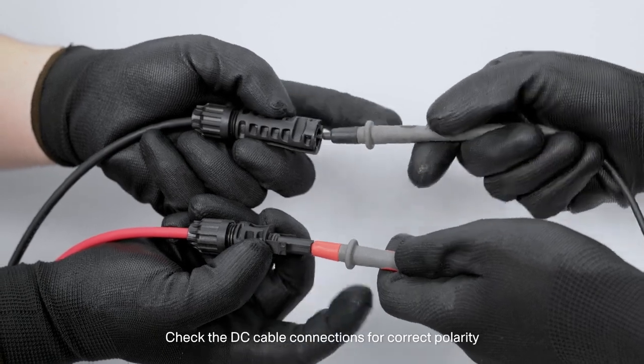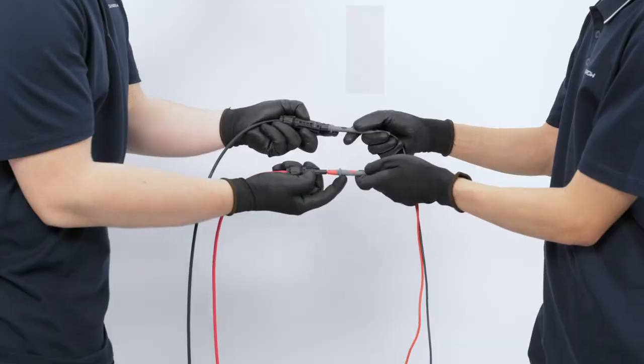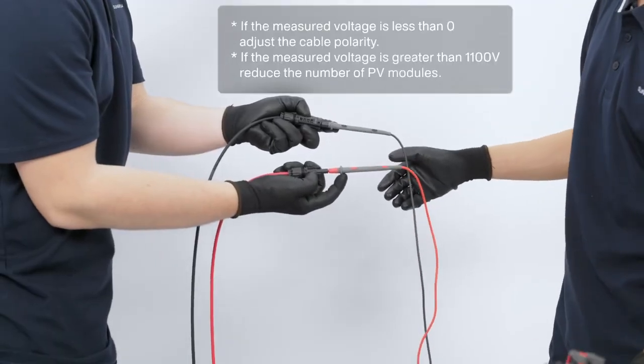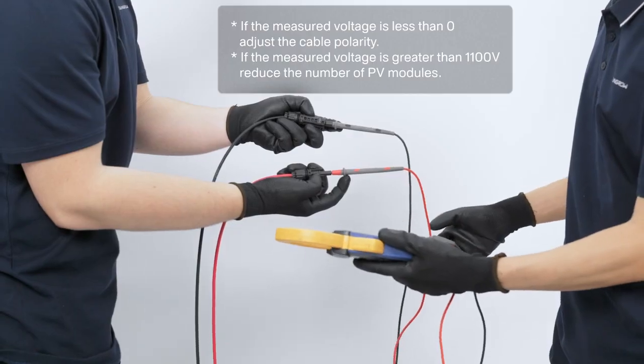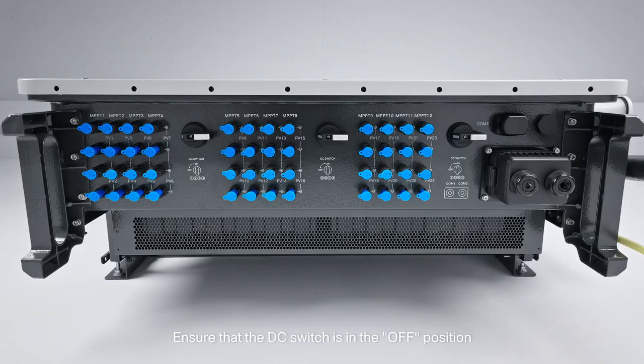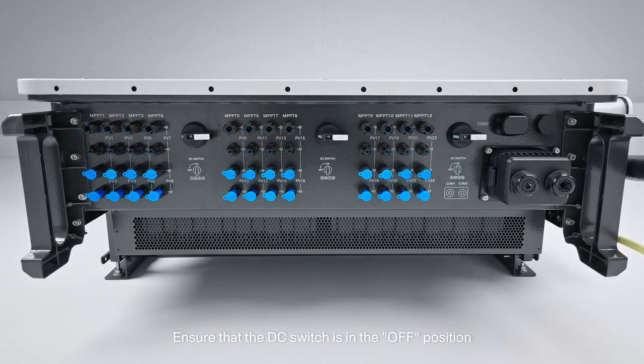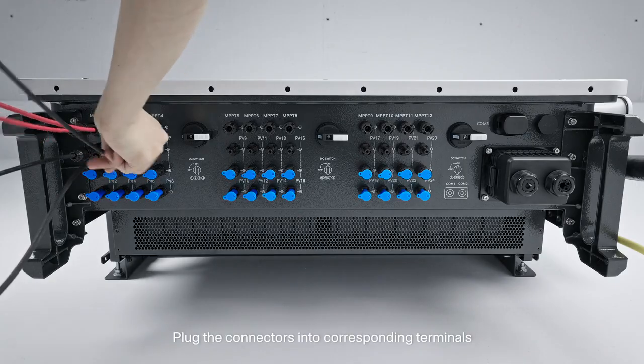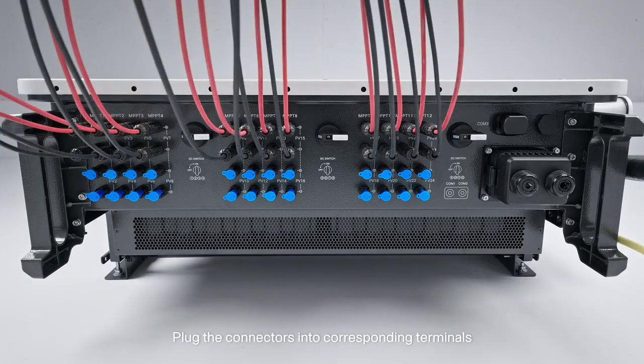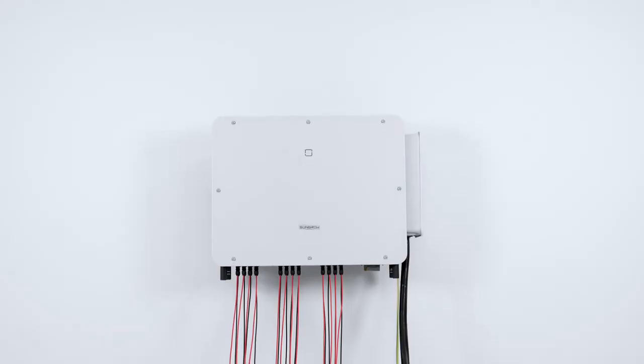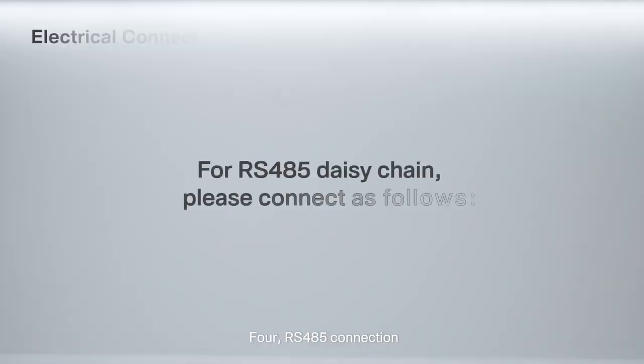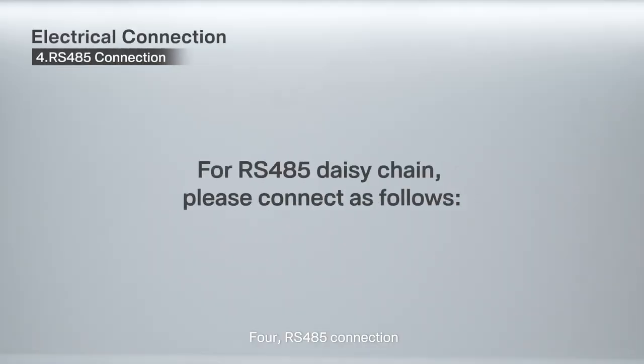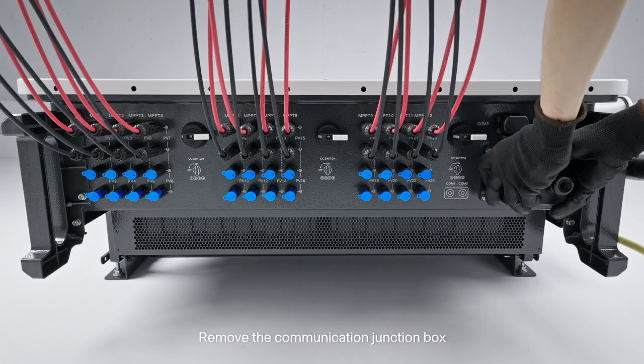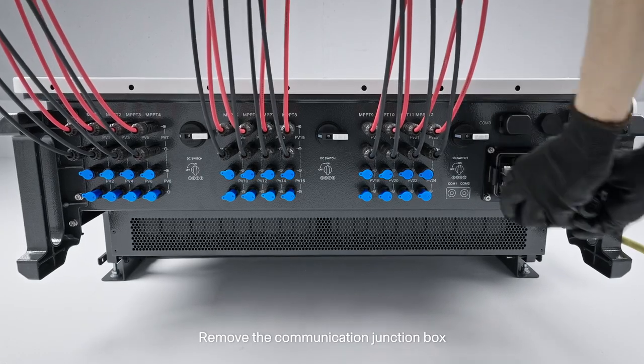Check the DC cable connections for correct polarity. Ensure that the DC switch is in the off position. Plug the connectors into corresponding terminals. 4. RS485 connection. Remove the communication junction box.